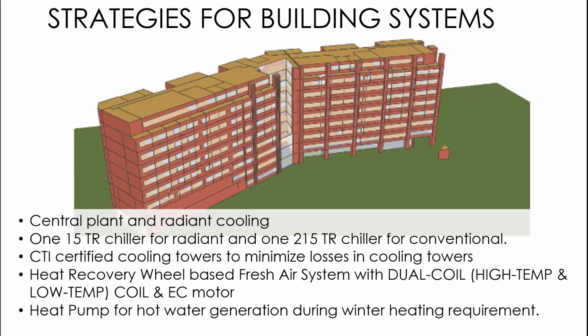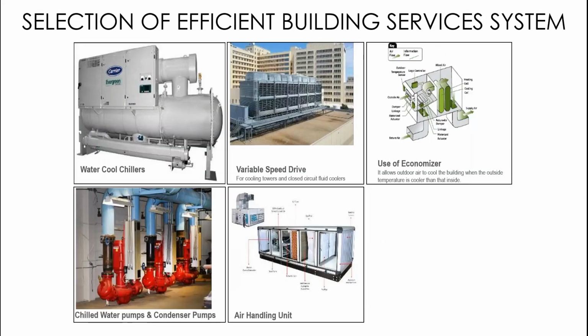Also, when we talk about pumping and chilled water pumping, there are different systems. Yeah, so when we talk about pumping, we are aware that there are chilled water pumps and condenser pumps for the cooling towers. In a typical conventional building, you will find primary pumps and secondary pumps. The primary pump is for pumping across the chiller, and the secondary is for pumping into the building.